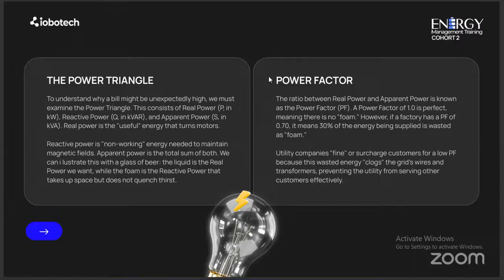Yes sir. Power factor is actually a figure which shows how efficiently a facility is using electrical energy supplied by the utility company. Majorly, when the power factor is lower, you do have surcharges imposed by your utility company because you are putting more stress on their generating devices like transformers and generators. This poor power factor is mainly caused by inductive loads like industrial arc furnaces and induction motors. So you need to minimize reactive power in the system caused by those inductive loads as much as they are required by those loads. You need to minimize them by bringing in devices to improve it so that it approaches one, to minimize losses in the system.